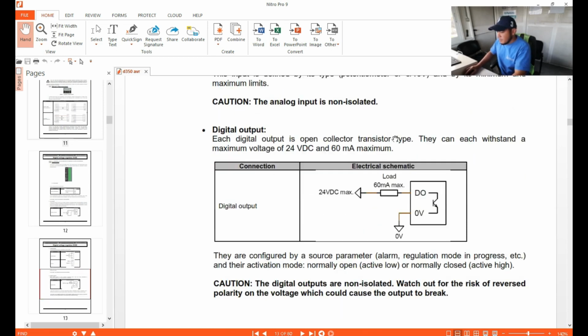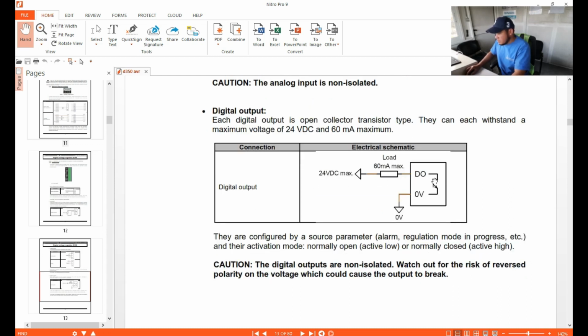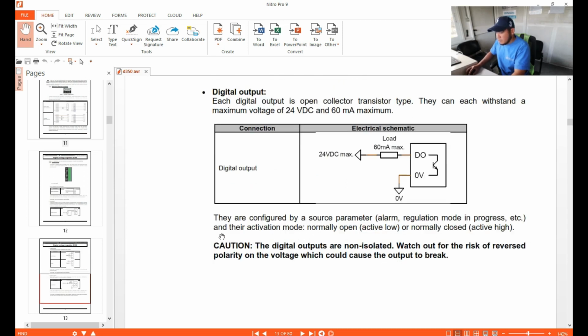Okay, so here also this one is digital output. So this is a maximum of 24 VDC only that you can apply. And here it is stated that this one is normally open. Let's read it. There are configuration parameters: alarm, regulation mode in progress, etc.. Normally open when it's active. So normally close is active high. Okay, so when active low, this one is normally open. When active high, it is normally close.